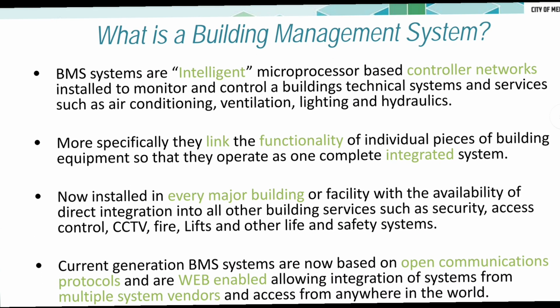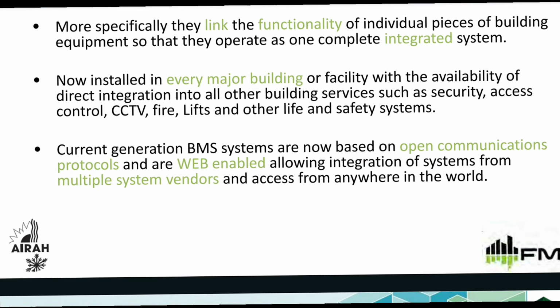What is a building management system? BMS systems are intelligent microprocessor-based control networks installed to monitor and control a building's technical systems and services such as air conditioning, ventilation, lighting and hydraulics. More specifically, they link the functionality of individual pieces of building equipment so that they operate as one complete integrated system. Installed in every major building or facility, with direct integration into all building services such as security, access control, CCTV, fire, lifts and other life and safety systems. Current generation BMS systems are based on open communication protocols and are web enabled, allowing integration of systems from multiple vendors and access from anywhere in the world.